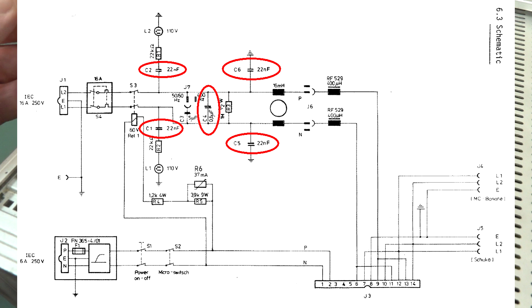If you find any old gear, vintage computers, or any other vintage test gear that uses these RIFA brand caps, or similar looking ones, for mains input filtering, either directly across the mains or down from active and neutral down to earth, then replace them. It's a real good idea because they might eventually go bangski.